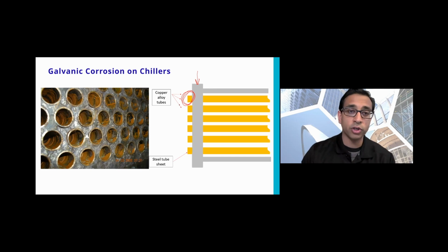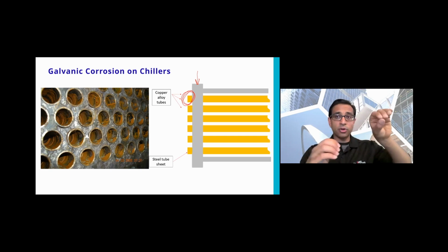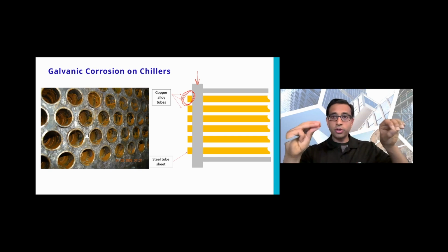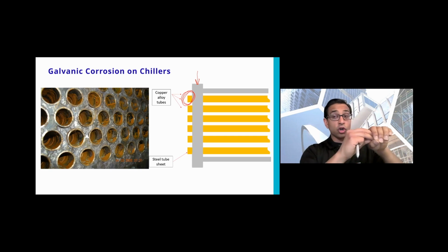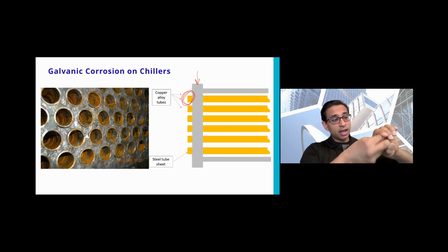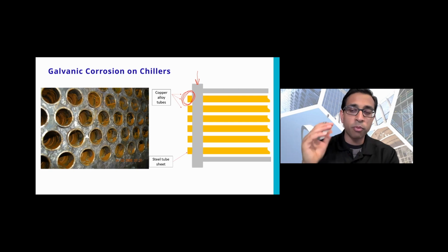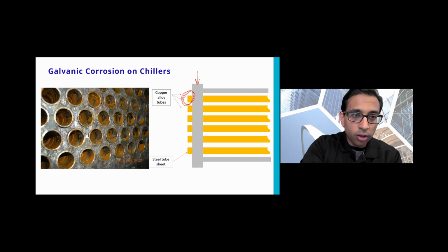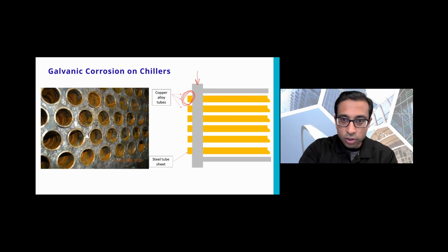So first, it's important to understand the construction here. Okay, so the way that these chillers are assembled, these alloy tubes actually slide into this stainless steel tube sheet, and when it slides in there, on the inside where they slide into, there's actually a tool that gets put in there. It's called a roller, and it actually expands the copper and then it's rolled in. So you get a completely tight seal. So all of this, like you look here, these are all rolled in place. There's no welding that's done to any of it. And so what happens is you have a roll that exists basically right in these areas right here.